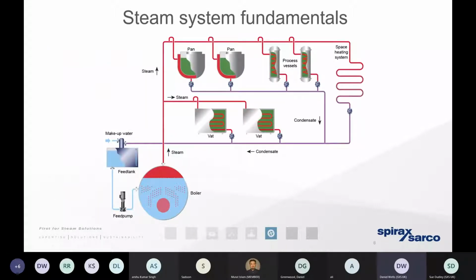So some of the terminology we use, you may have noticed that I mentioned the steam and condensate loop. That's because we generate steam in a boiler house, in an energy centre, and that could be located hundreds, if not thousands of meters away from the various processes or plant rooms that are going to use that heat energy. So if you think about an oil refinery or a large hospital, we can be distributing the steam some considerable distance. And that's one of the reasons why we want to ensure that we're generating the best possible condition of steam that we can. It's only by doing so that the steam is going to arrive at the point of use in the best possible condition.